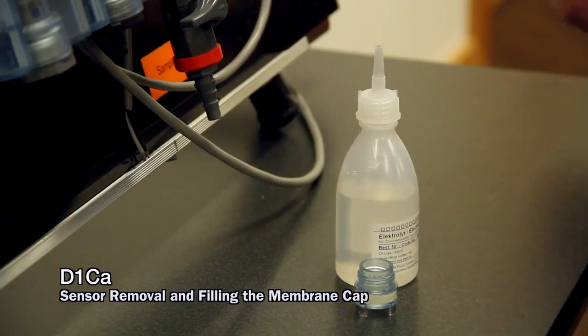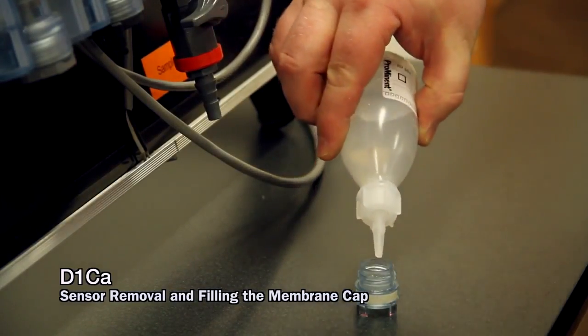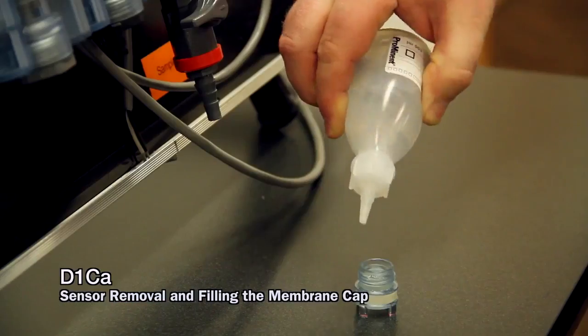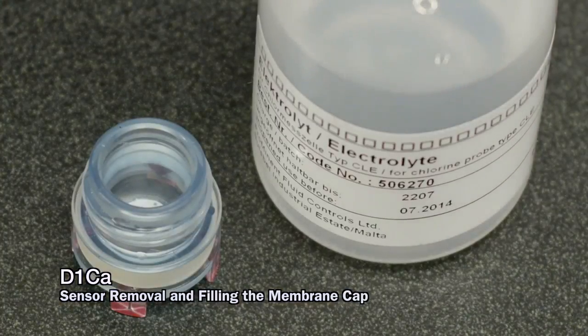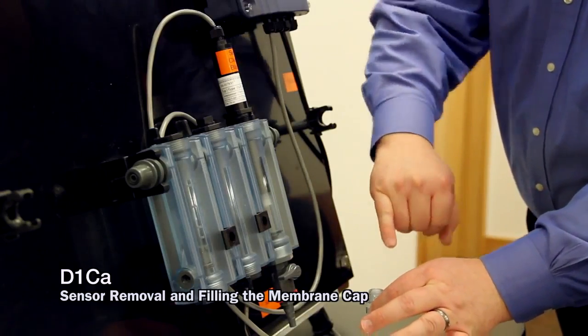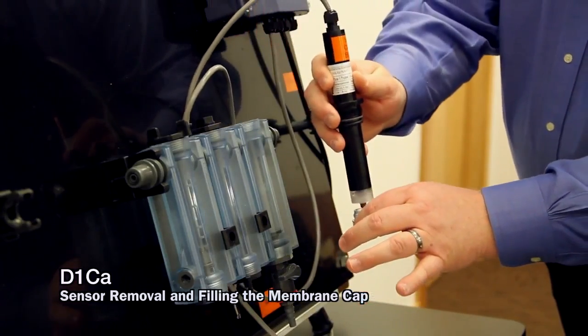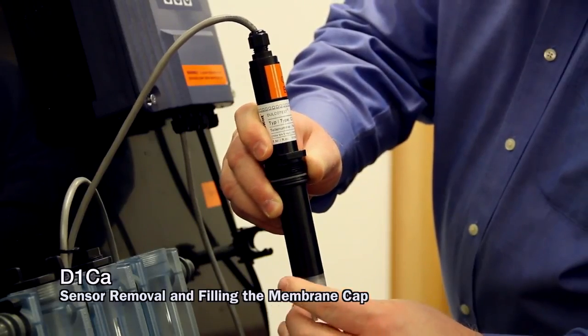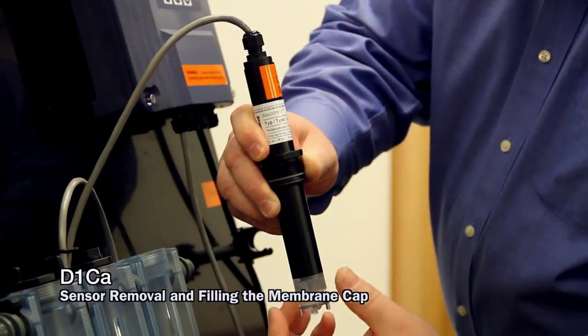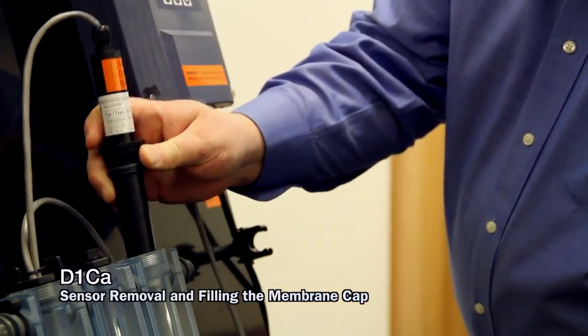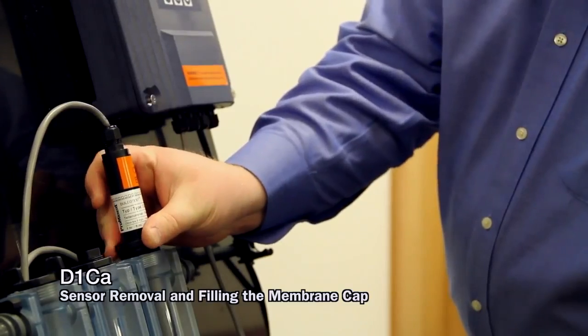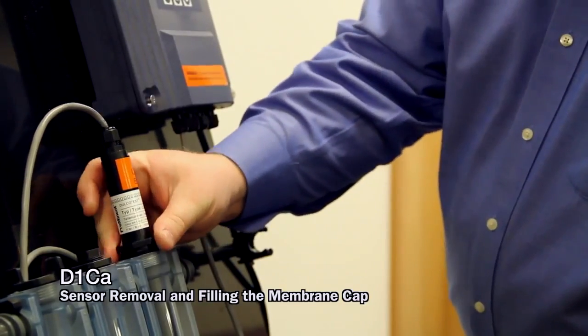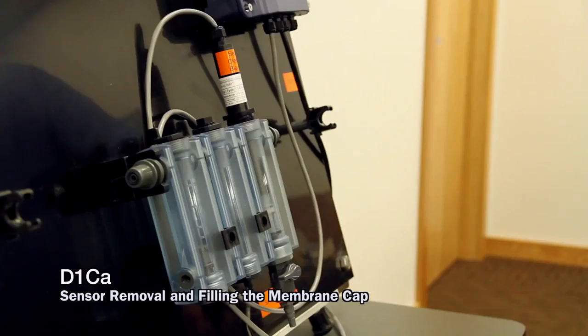Now this particular sensor has a very water-like electrolyte. We're going to fill that cap full. Be sure that there are no air bubbles down where the membrane is inside of the cap. Thread that cap back onto the sensor. Place the sensor back into its sample cell and tighten our compression fitting back in place. We can now start flow in the sample line. After we've changed the electrolyte, or if we first installed the electrolyte, it takes several hours to get a true reading before we want to do our calibration.